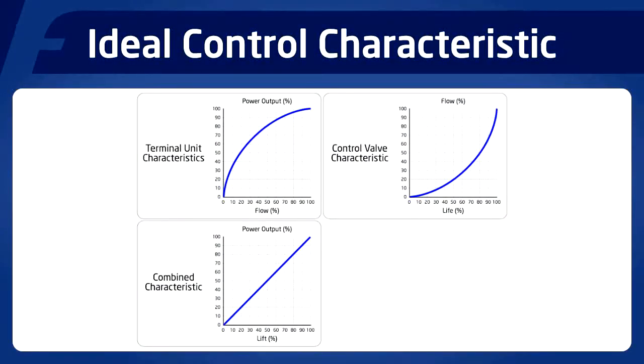The graph on the bottom left of the slide shows that when the power output and flow characteristics are combined, the result is a proportional relationship between valve lift or feedback signal from the temperature sensor and power output from the coil, leading to proportional control of the temperature.